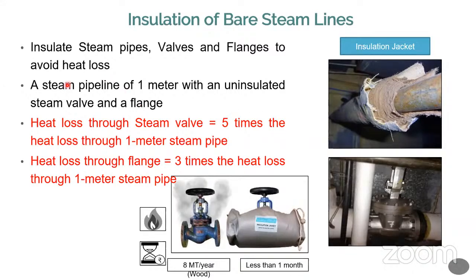So the steam pipeline should be properly insulated. For 1 meter of steam pipeline with uninsulated steam valve, there is a problem. You can see the heat loss through the steam valve is 5 times the heat loss through 1 meter of steam pipeline, and similarly the heat loss through the flange is equal to 3 times the heat loss in 1 meter of steam pipeline. So it is measured like this.